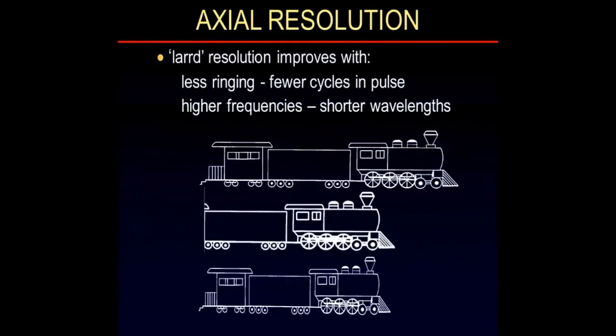So here's the story with axial resolution. The top train, the train is long. I have 3 cars in my train. I have 1, 2, 3 cycles in my pulse. The pulse is long. My axial resolution is poor. So what do I do? I put down that transducer and I pick up a transducer that creates the second pulsing pattern. Here, this has 1, 2 cars in the pulse. So the pulse is shorter.